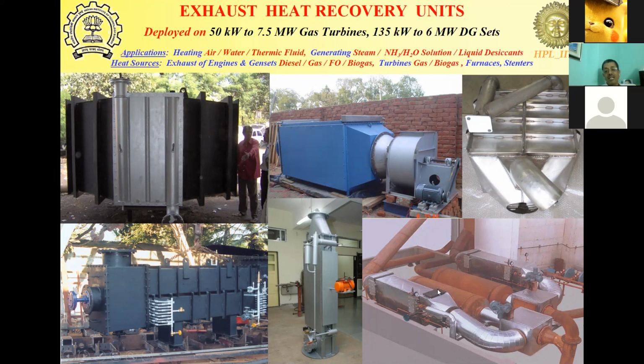By the way, my client had deployed around 60 installations of genset exhaust heat recovery, from 135 kilowatt to 6 megawatt single engine. And in some of the locations, there were three 6 megawatt engines fitted with our exhaust heat recovery units for generating steam. We have also developed recuperators for gas turbines, for micro gas turbines.